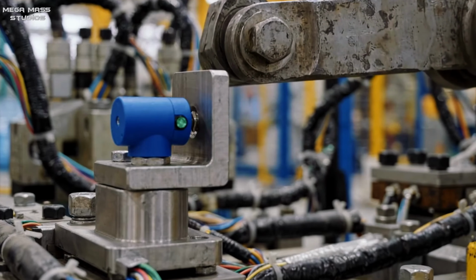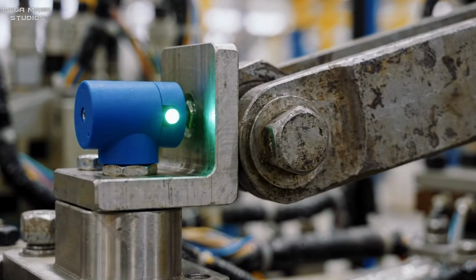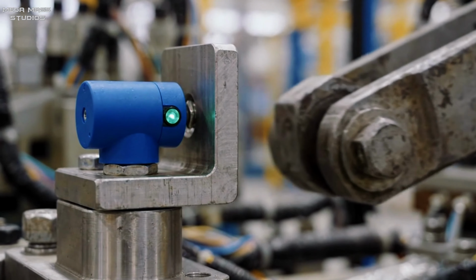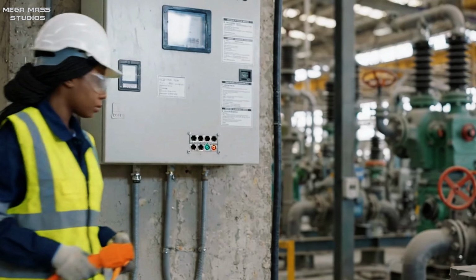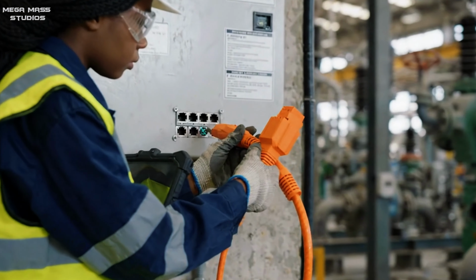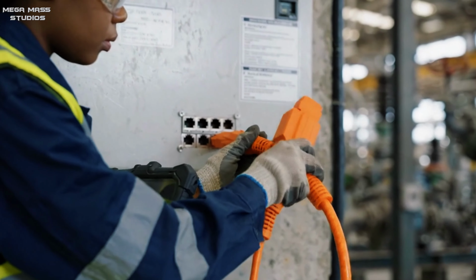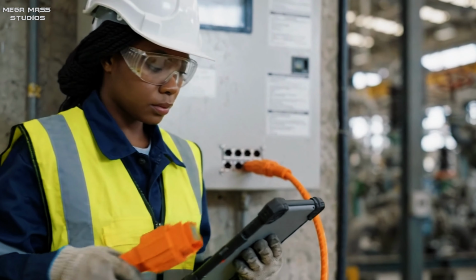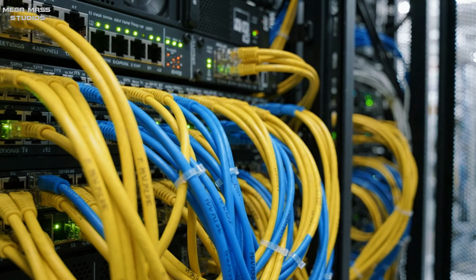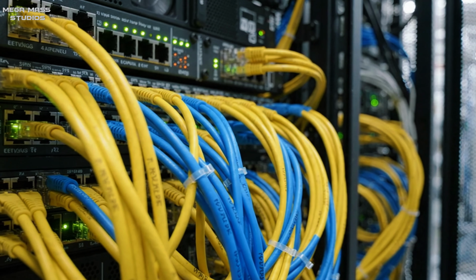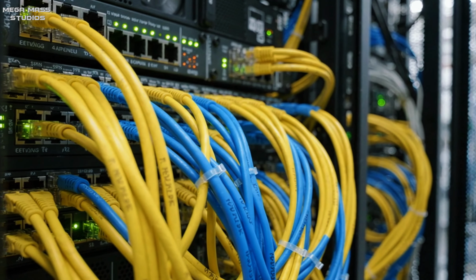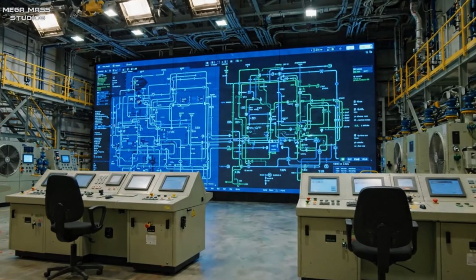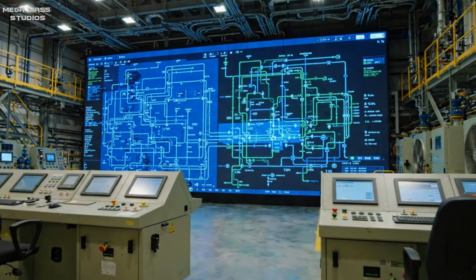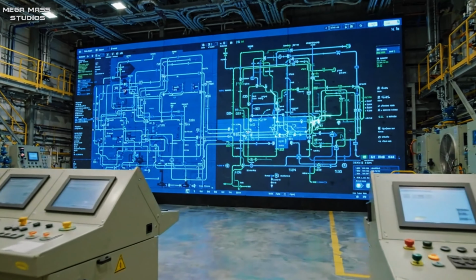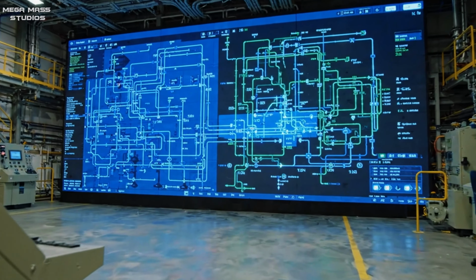The operational state of these critical valves is tracked by heavy-duty non-contact inductive proximity sensors. These sensors output digital signals directly to the localized remote terminal units located inside the pump house. From these terminal units, the data travels along fiber optic rings directly to the central control room. This main command facility utilizes a high-availability SCADA system to supervise the entire subterranean water network.